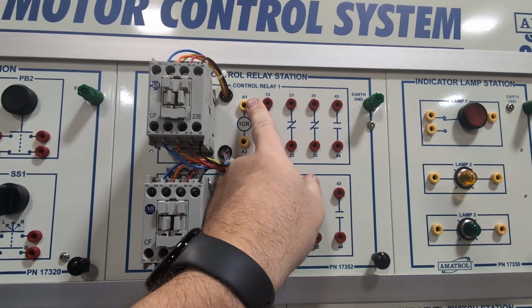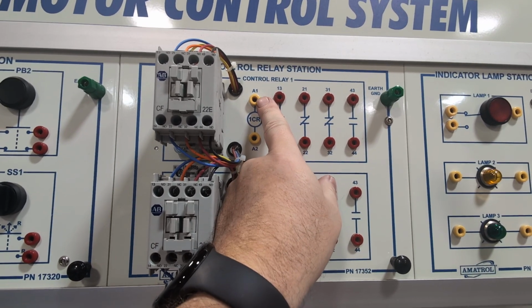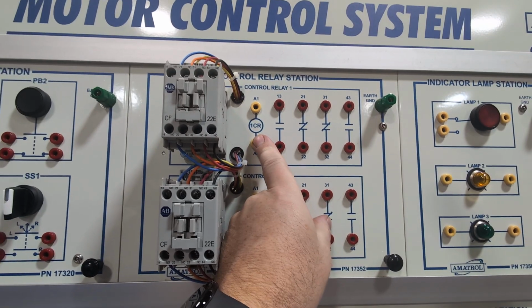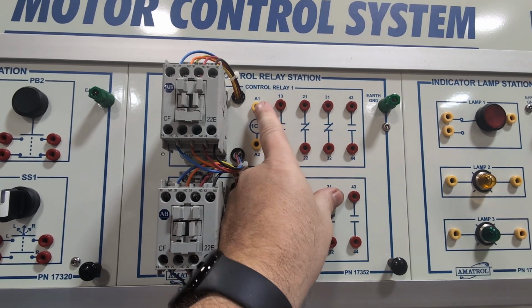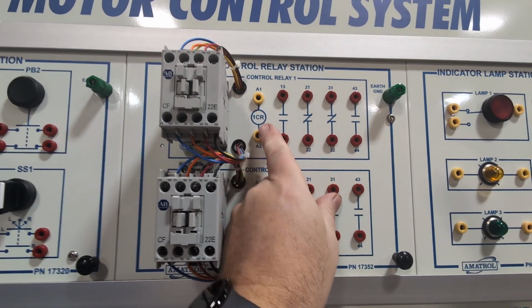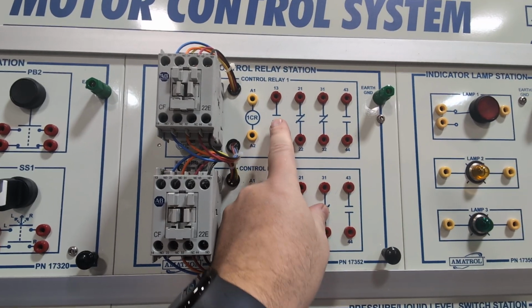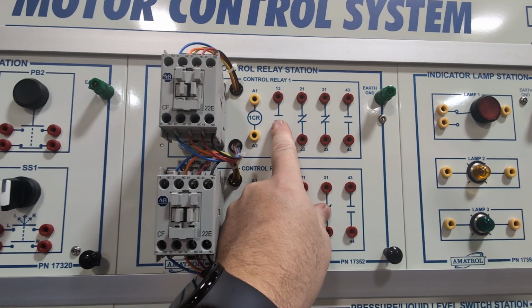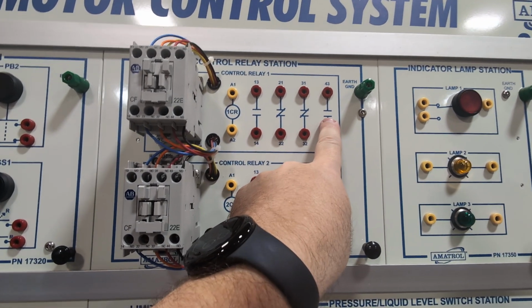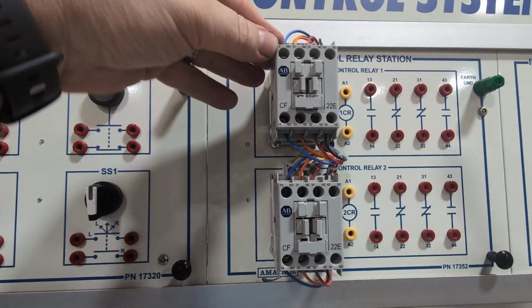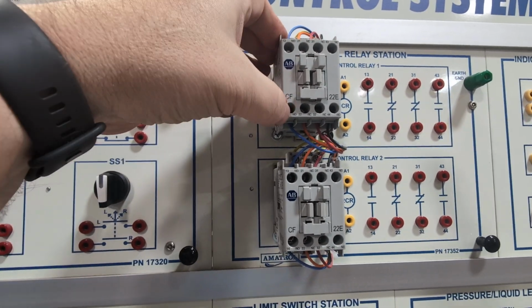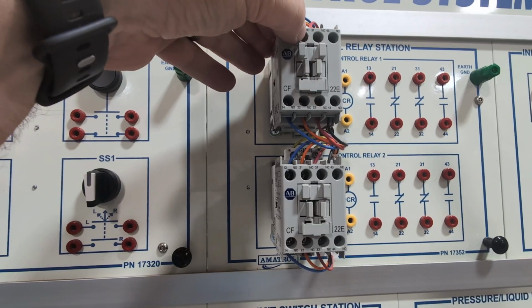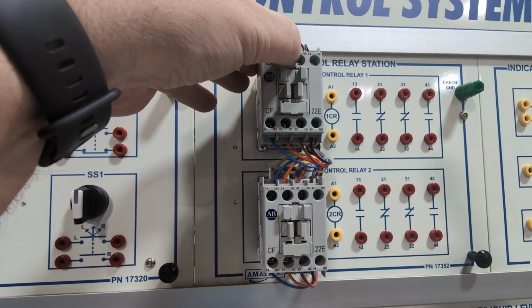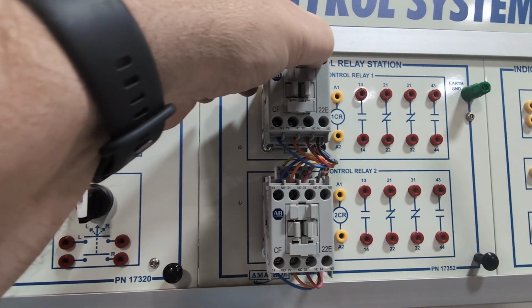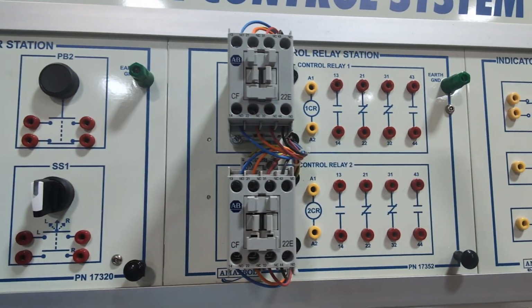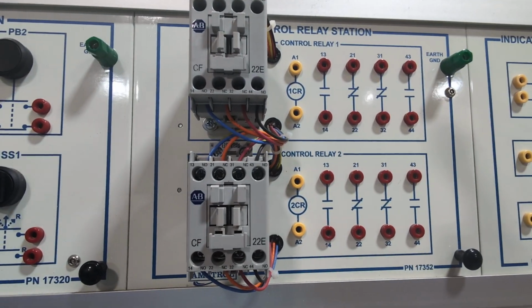A1, A2. A1, if you're doing 120 volts, would be your hot. A2 would be your neutral. With 24 volts, this would be my positive 24, negative 24. If you notice here, this is a normally open, normally closed, normally open. You look in the front, it says normally open, NO, normally closed, NC, normally closed, NC, normally open, normally open. That is called a control relay.